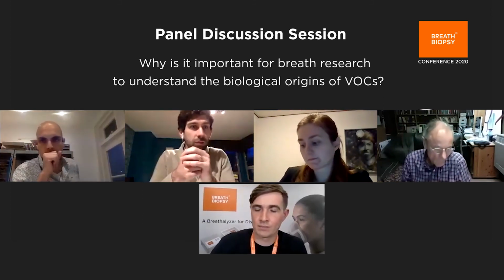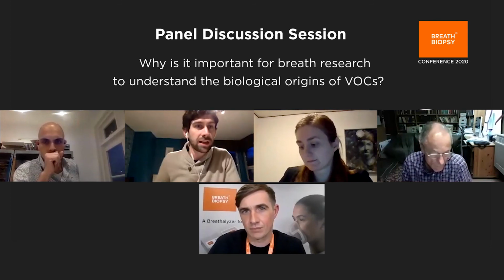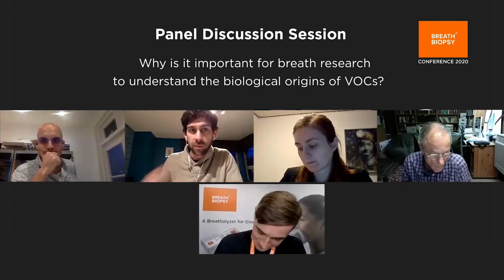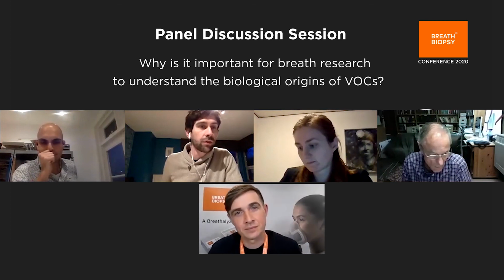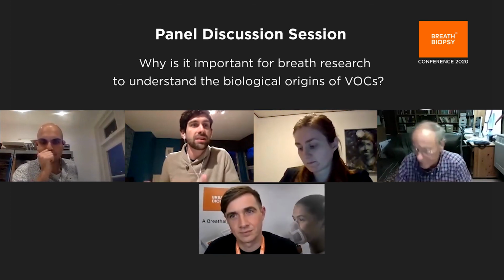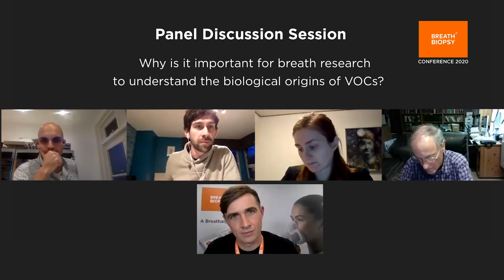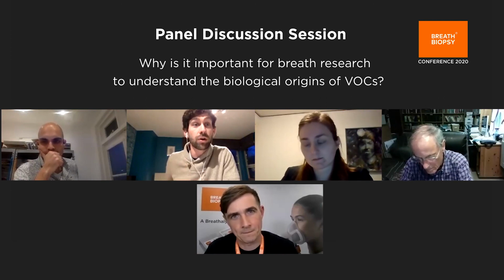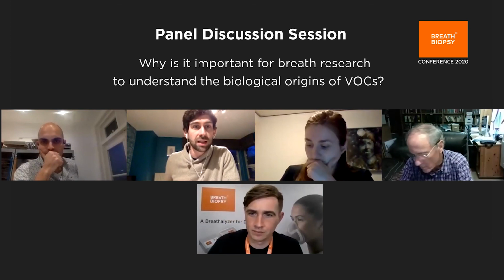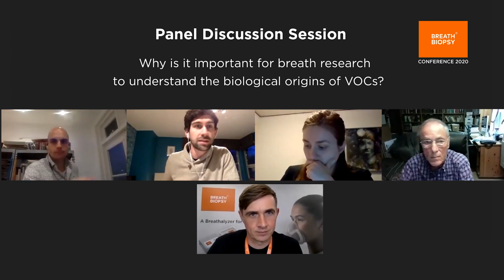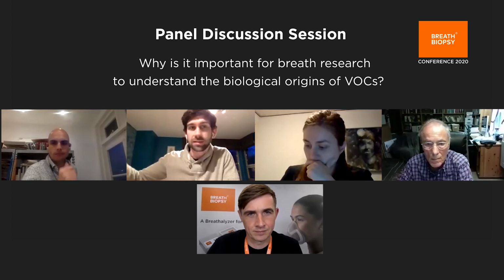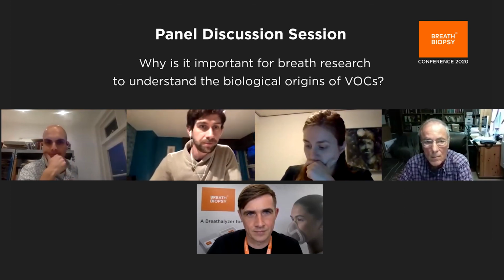I know that we cannot generate a pool QC of breath, it's difficult. We don't have reference material for breath, but we have to be creative, using some gaseous standard to monitor instrument stability, and make sure that we don't have over time batch effects and all these things that we know will happen, but they are more difficult to track with VOCs. So I think if we keep control of the analytical process and the data processing side, we will improve the robustness a lot. And it's there that we can start to build something strong and progress in compound identification and sensor building and everything.